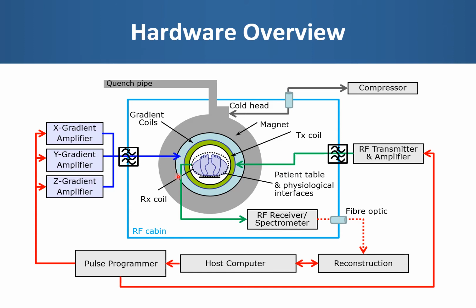Then we have the receiver coils, which are generally arrays of small elements that are positioned as close as possible around the anatomy of interest of the patient, and each of these individual coil elements are then connected to a radio frequency receiver and spectrometer system, where the analog signals from the coils get digitized and then transferred over fiber optic out through the RF cabin through waveguides into a separate reconstruction computer.